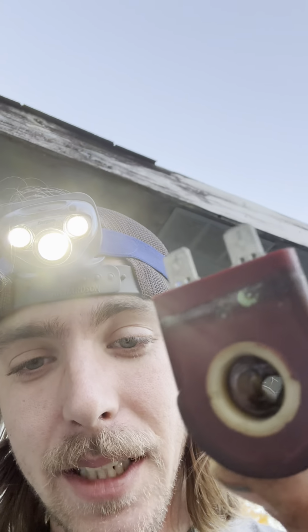So what I'm gonna go do next is I'm about to go rob the graveyard that I have, because I've been changing 30-year-old units out all freaking year. So I'm gonna go see if I can rob one off an old unit. In the unfortunate event I cannot find the solenoid, the customer can still run it on heat strips. Just make sure it's on emergency heat. Just make sure you do not cut on the outdoor unit, because as soon as I cut on the outdoor unit and I hook these two tabs up, it blows the fuse and everything quits working. So I'm gonna go see what I got.